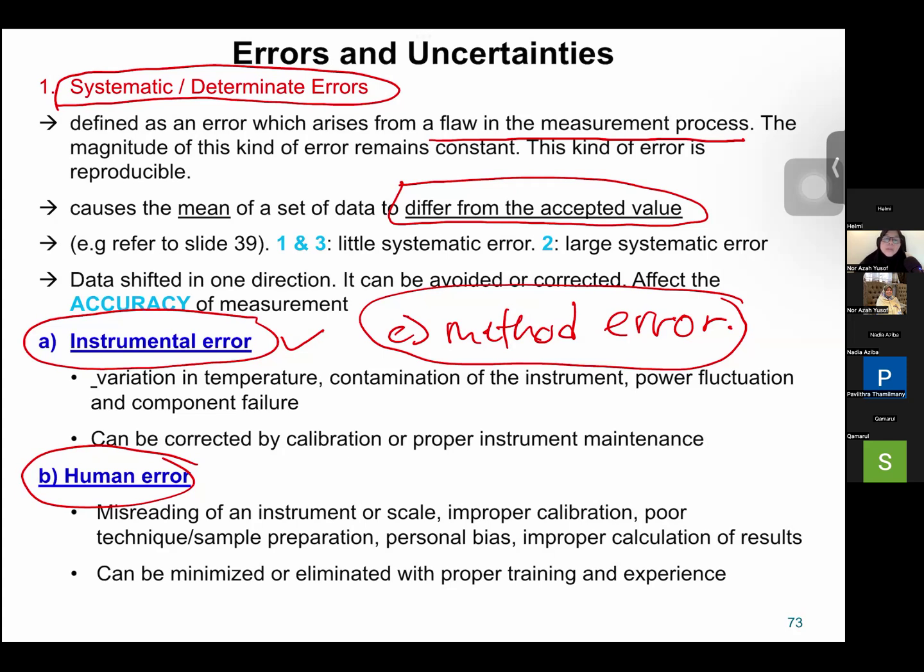Yes, true. So that's why maintenance and verification of machines is very important. Even though it's expensive, you have to do calibration and proper maintenance. If it requires some verification, some calibration, please do, and check whether it gives correct results based on standard material.